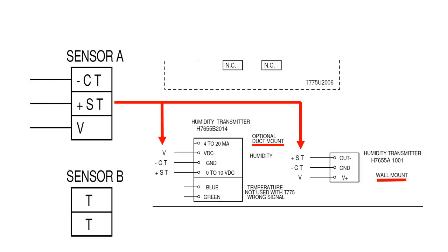Both wall and duct mounted sensor connections are provided and are connected as seen here. Unusual humidity readings are often an indication that the sensor was wired incorrectly.